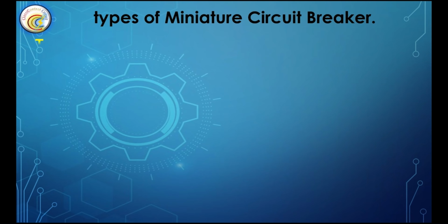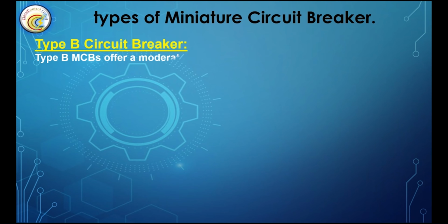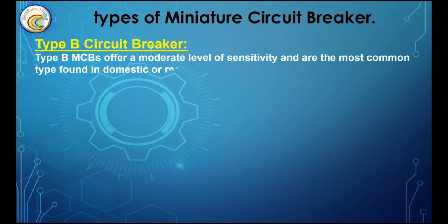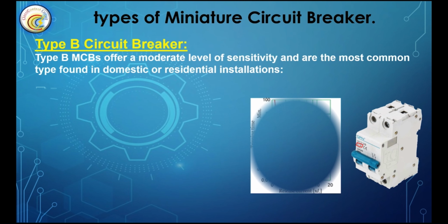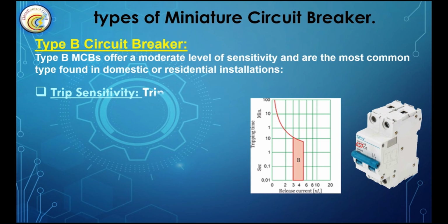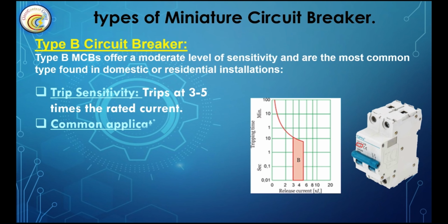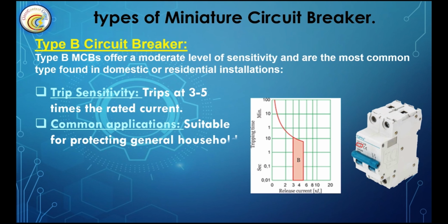Type B circuit breaker. Type B MCBs offer a moderate level of sensitivity and are the most common type found in domestic or residential installations. Trip sensitivity: trips at 3 to 5 times the rated current. Common applications: suitable for protecting general household circuits, including lighting, sockets, and small appliances like refrigerators and washing machines.